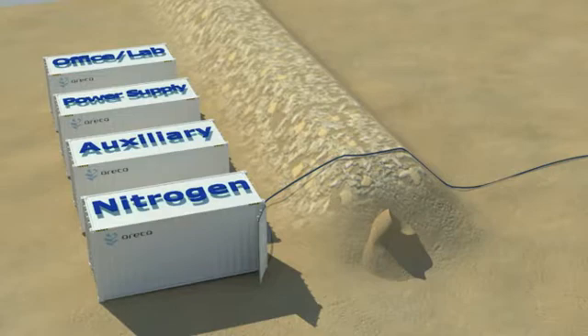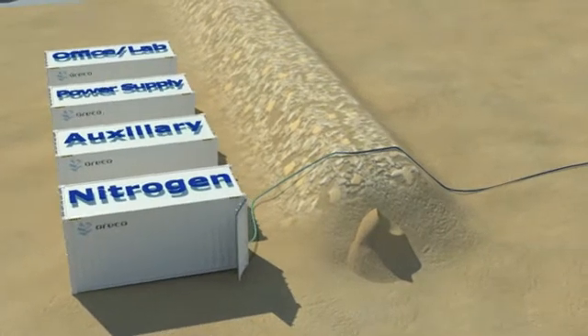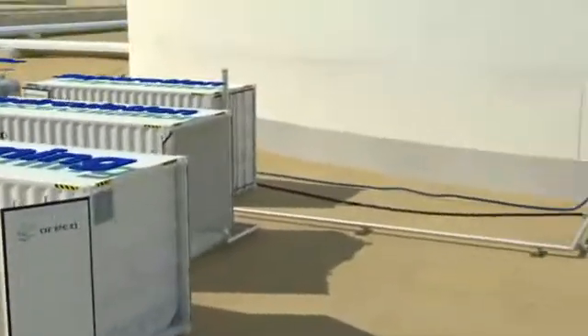Pipes, fittings, oil distributors and Areco specially designed patented nozzles are lifted onto the rooftop. All equipment on the roof and inside the tank is approved for use in these potentially hazardous zones. To avoid risk of explosion, an inert gas, typically nitrogen, is injected into the tank to reduce the oxygen level to below 8%. This level is maintained throughout the entire tank cleaning process.